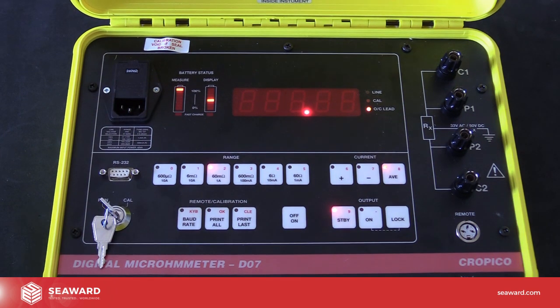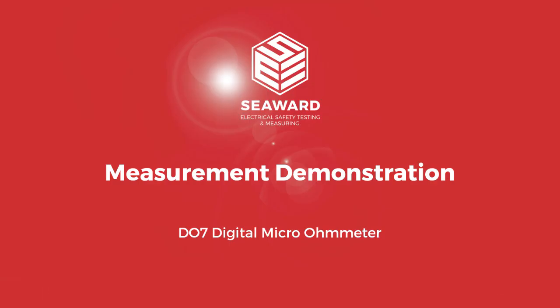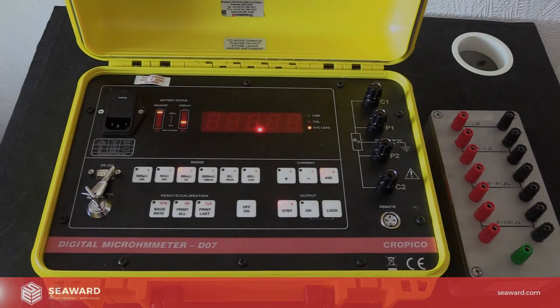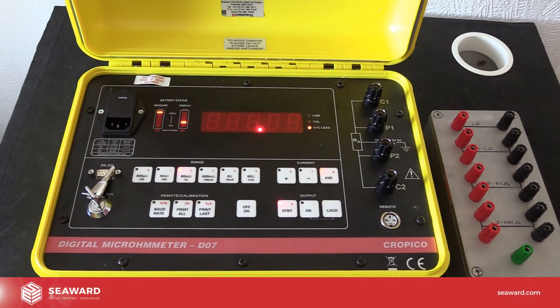When actually performing measurements, the DO7 can be set to either take a single measurement at the point of press, or we can set the unit to a continuous mode, in which case it is constantly measuring the resistance. So for this demonstration, we're going to be using a highly accurate resistance box to simulate a measurement in the real world. Firstly, we need to take our connections.